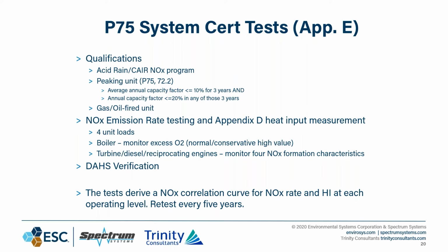You'll be tested at 4 distinct unit loads. And if you're a boiler, you'll monitor your excess O2, looking to determine a normal or conservatively high value. If you're a turbine or a diesel or reciprocating engine, you have to monitor your NOx formation characteristics, whatever combination of 4 parameters.